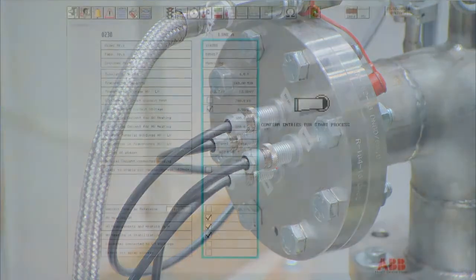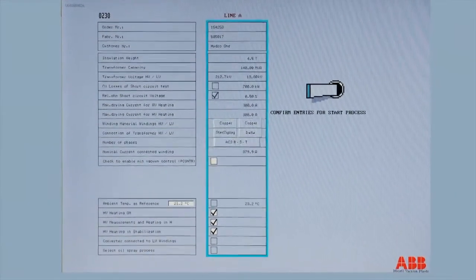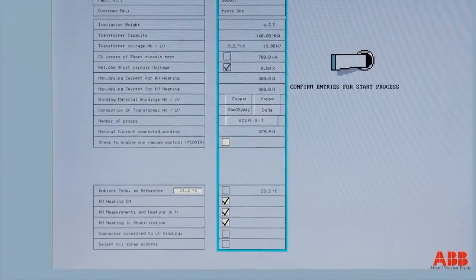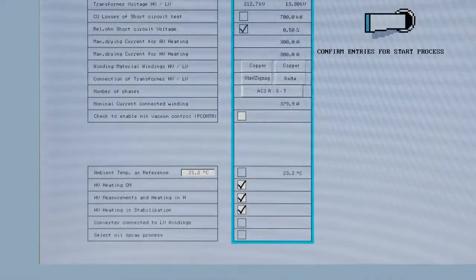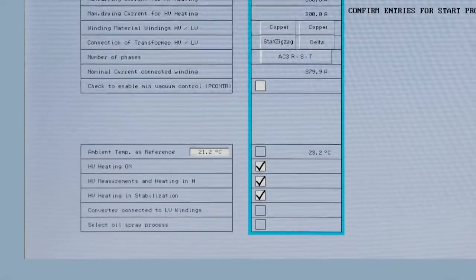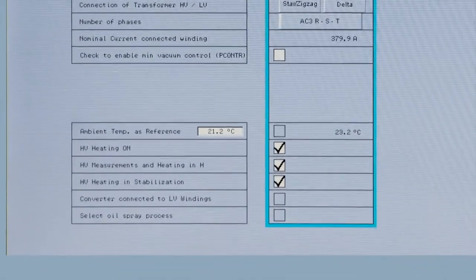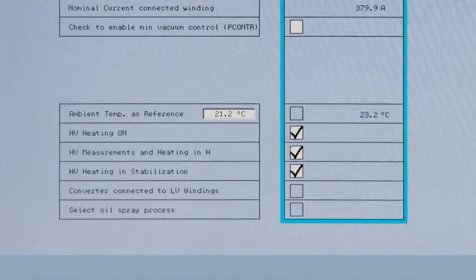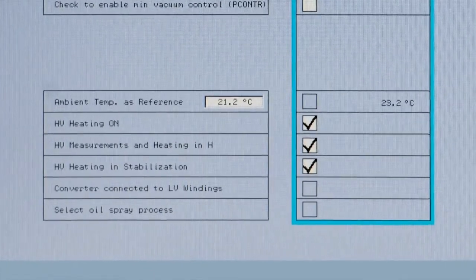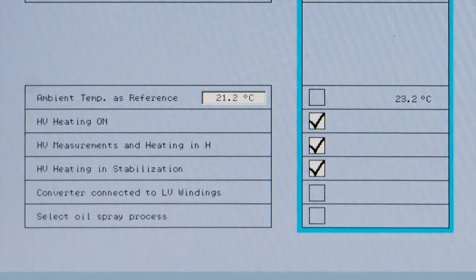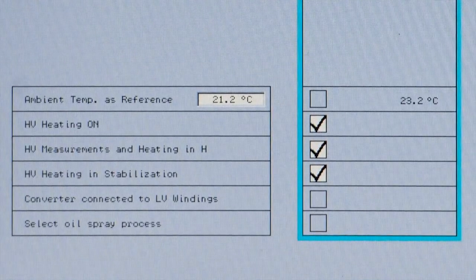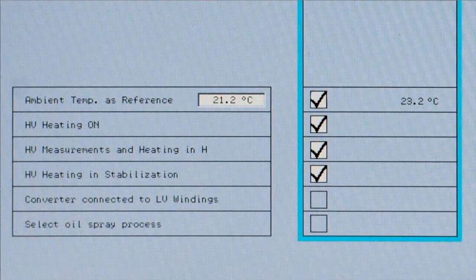The initial temperature of the transformer can be taken automatically from the temperature sensor, which is mounted inside the container. There is also the possibility to enter the temperature manually by clicking the checkbox. Then the actual temperature for the transformer can be entered, and this value will be used as the reference value for the transformer during the heating. It is essential that the correct value for the transformer temperature is used. In other cases, there is a risk of overheating the transformer.